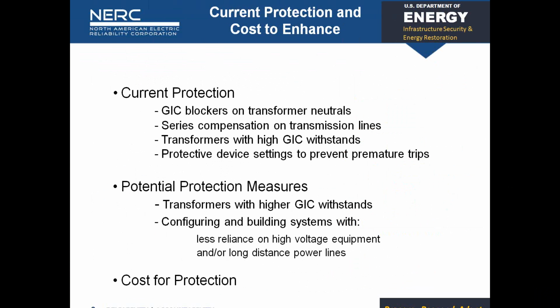It's kind of expensive. After doing assessments, I expect we'll see some more of those go in. Series compensation is another way, actually on the power line, as opposed to blocking it from coming into the transformer. At the transformer neutral, you can put capacitors on the power lines to prevent the DC current from flowing through. Series compensation on power lines is typical in a lot of the western part of the country.